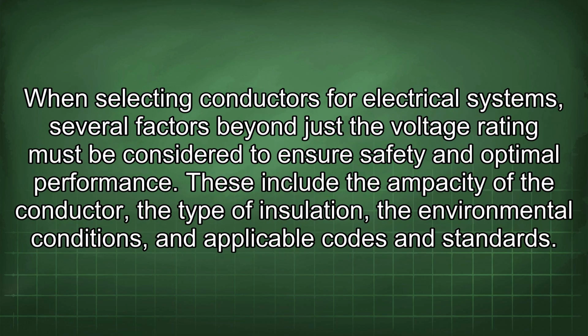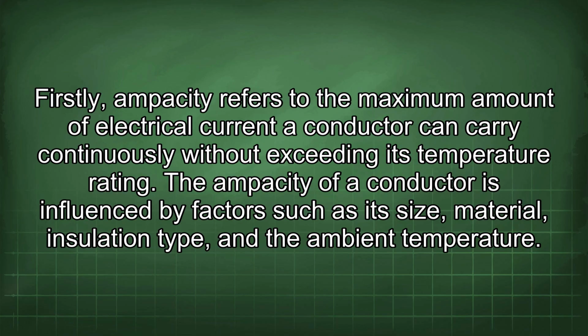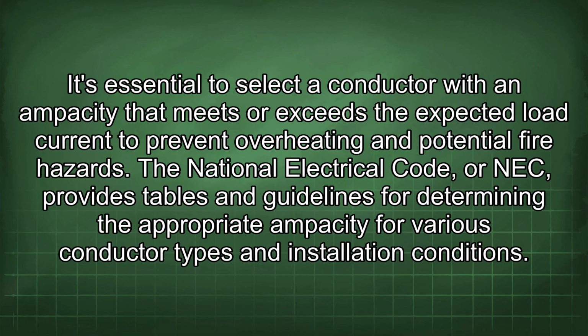When selecting conductors for electrical systems, several factors beyond just the voltage rating must be considered to ensure safety and optimal performance. These include the ampacity of the conductor, the type of insulation, the environmental conditions, and applicable codes and standards. Firstly, ampacity refers to the maximum amount of electrical current a conductor can carry continuously without exceeding its temperature rating. The ampacity of a conductor is influenced by factors such as its size, material, insulation type, and the ambient temperature. It's essential to select a conductor with an ampacity that meets or exceeds the expected load current to prevent overheating and potential fire hazards.